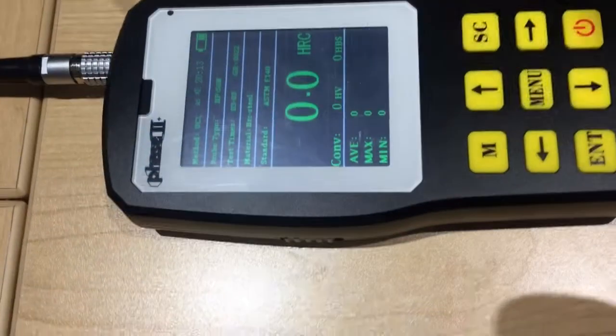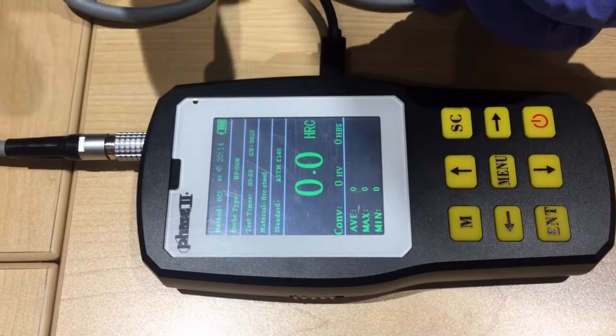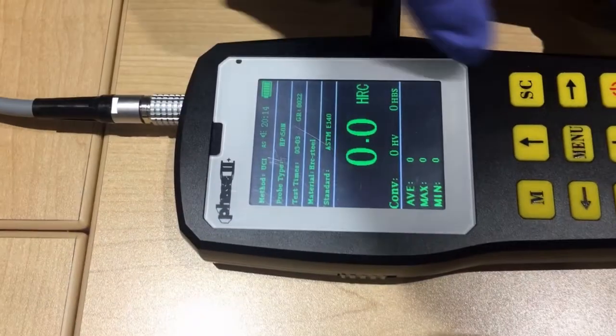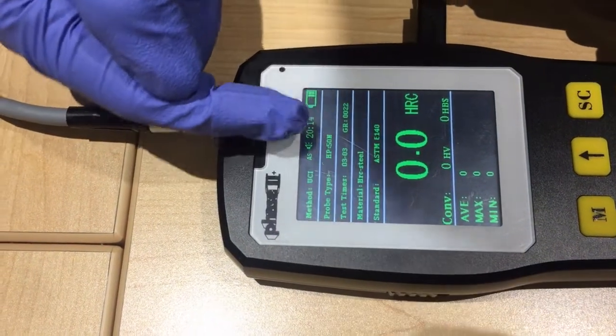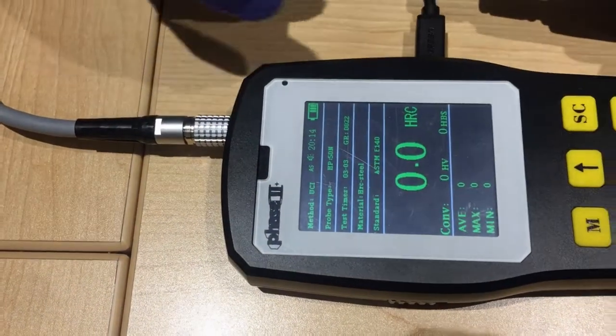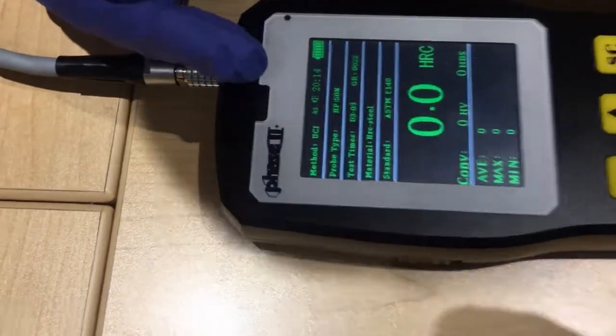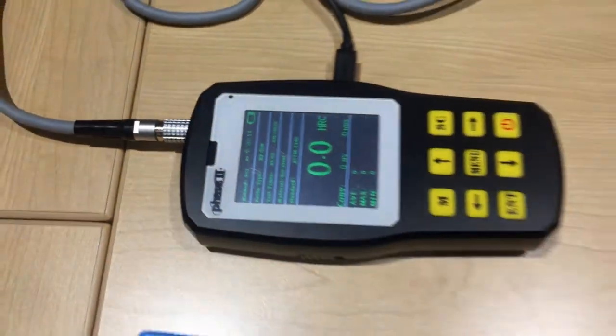If the probe is not correctly linked, we can see on the machine here, probe type, it will show an arrow. And here we can see it's HP 50 Newton, so it's correctly connected.